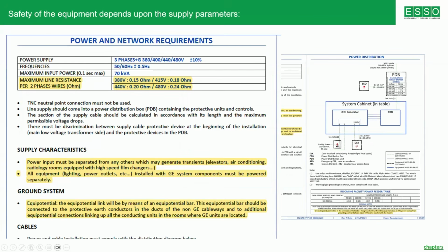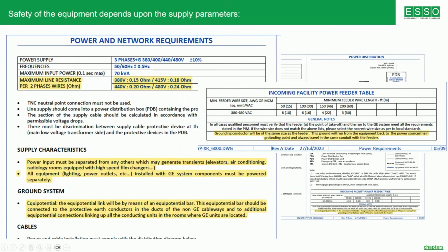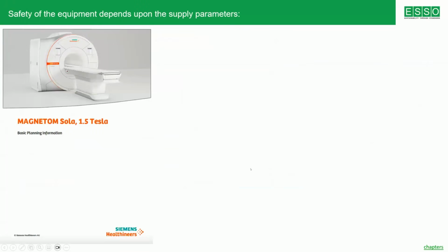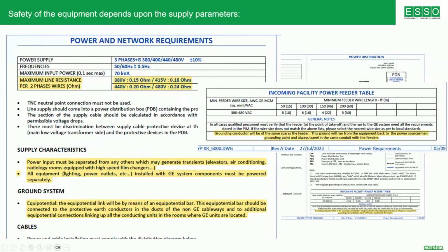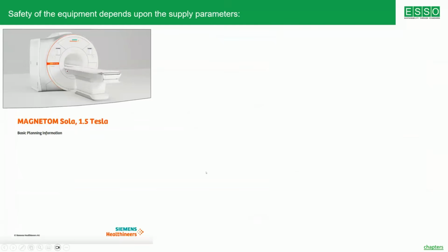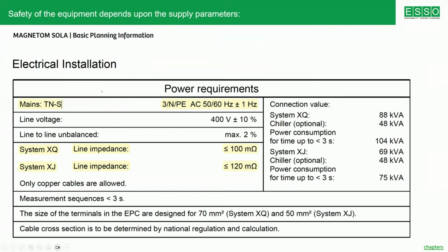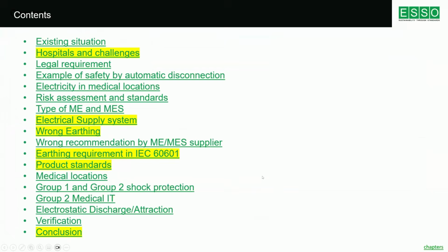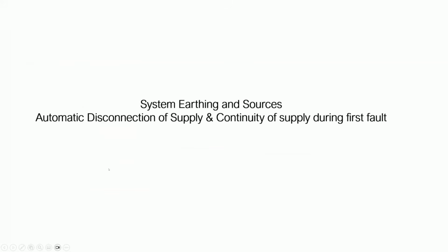Example, equipotential. Equipotential link will be by means of an equipotential bar. Grounding conductor will be of the same size as the feeder. That means in a normal electrical installation, we say if the line conductor is more than 35 millimeter square copper, the protective earth conductor can be half the size. Whereas for this particular equipment, this is not applicable. You have to size it as per the same size of the line conductor. Another equipment is suitable for a TNS system. The line impedances are measured. So basically, these requirements are part of the product standard. So the first job is to understand and find out the electrical requirement, the earthing requirement, and the safety requirement of the electrical equipment which you are going to use in your electrical installation of the hospital.